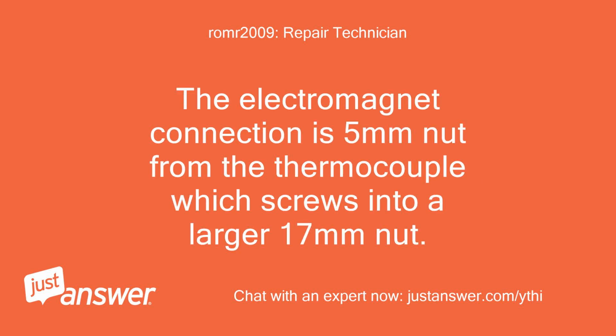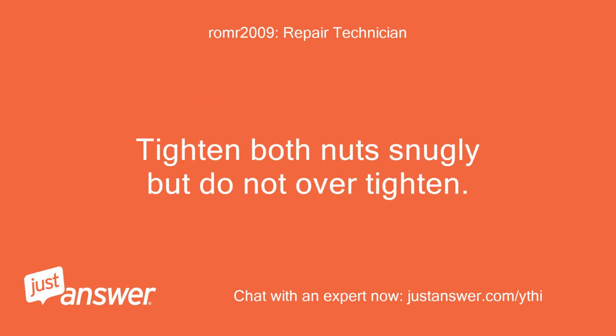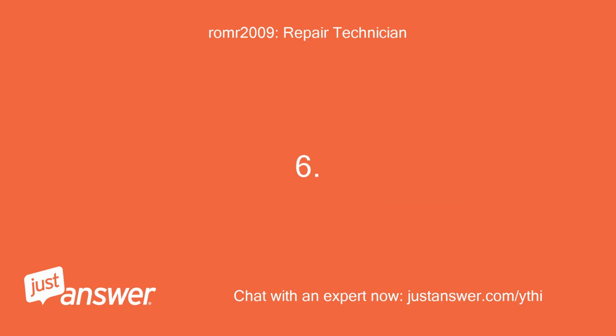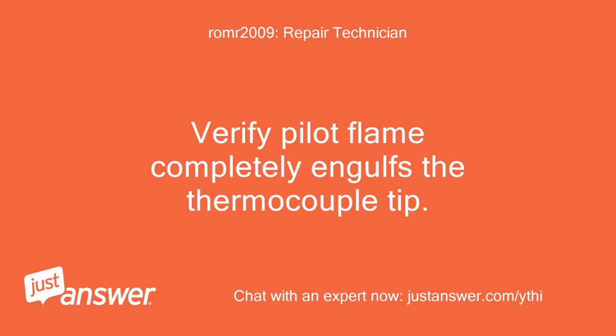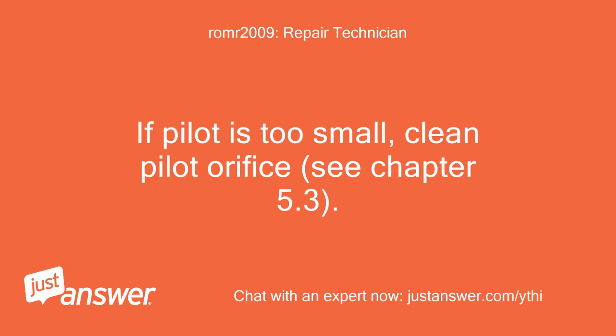The electromagnet connection is 5 mm nut from the thermocouple which screws into a larger 17 mm nut. Tighten both nuts snugly but do not over-tighten. 6. Verify pilot flame completely engulfs the thermocouple tip. If pilot is too small, clean pilot orifice, see Chapter 5.3.